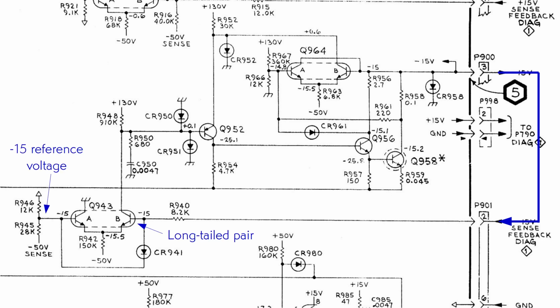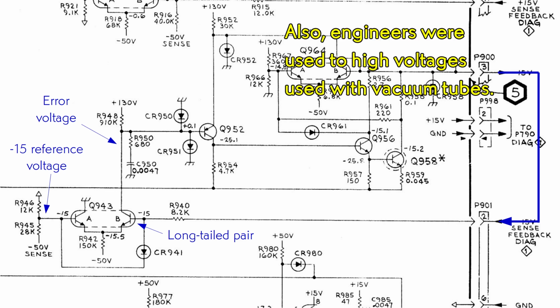The sensed voltage comes into a long-tailed pair, whose other input is a negative 15 volt reference derived from the negative 50 volt supply. The pair generates an output voltage proportional to the difference between these voltages, the voltage error at the load. By the way, the huge voltages and correspondingly huge resistors were pretty typical of devices of the period. The resistors functioned as high-impedance current sources—transistors were too expensive to squander on delivering small constant currents.